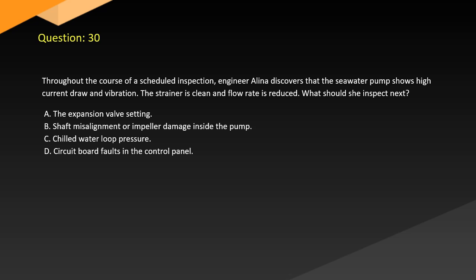Question 30. Throughout the course of a scheduled inspection, engineer Helena discovers that the seawater pump shows high current draw and vibration. The strainer is clean and flow rate is reduced. What should she inspect next? A. The expansion valve setting. B. Shaft misalignment or impeller damage inside the pump. C. Chilled water loop pressure. D. Circuit board faults in the control panel.